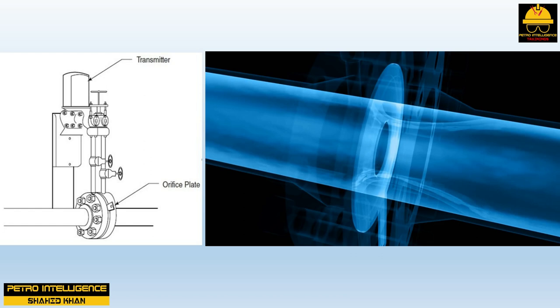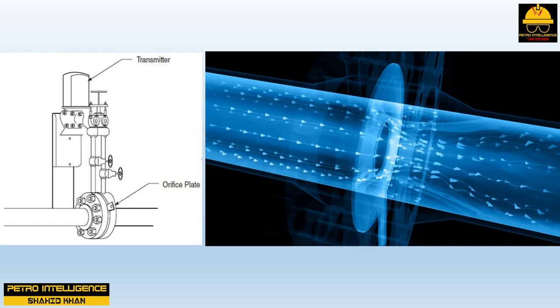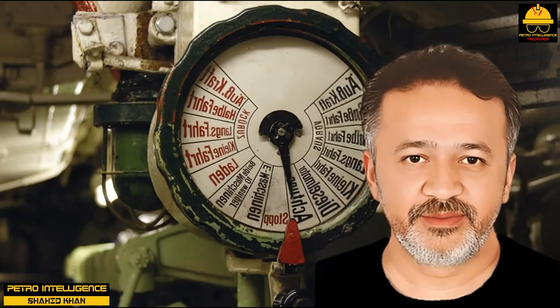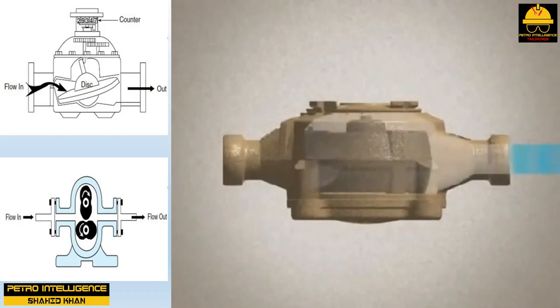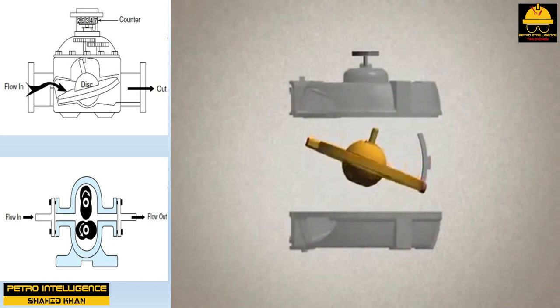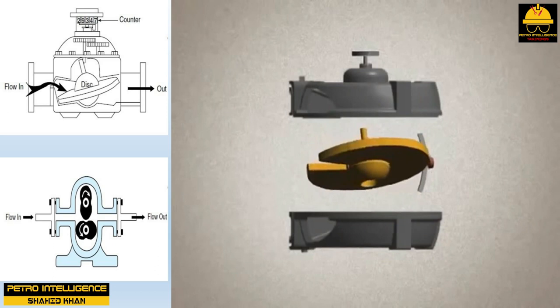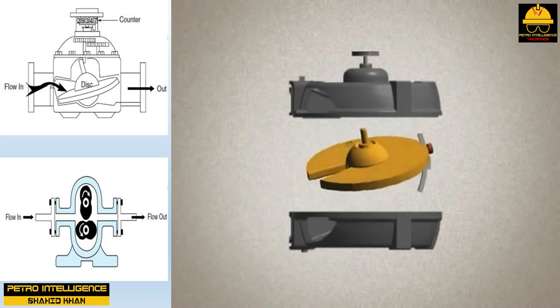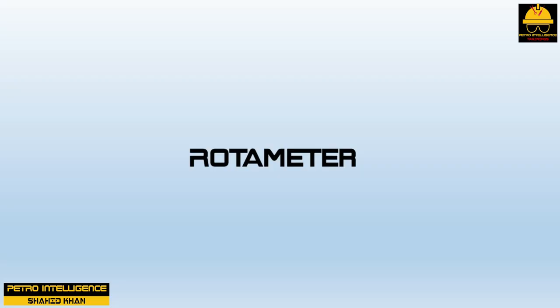Controllers send signals to control valves to open or close depending on the comparison of the signal from the field with the flow rate set point. There are two types of positive displacement meters: nutating disc and oval gear. A nutating disc meter measures fluid flow directly by counting rotations of the disc as fluid passes through it. An oval gear meter has an internal structure resembling a lobe pump; the lobe-shaped elements rotate as fluid passes through the internal chamber, and the rotation of the gears is used to calculate total flow rate.